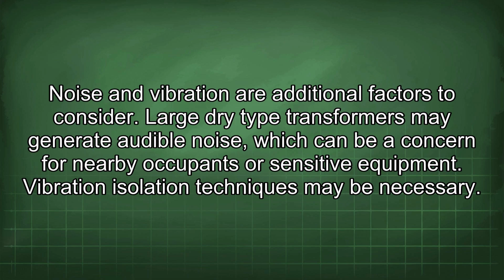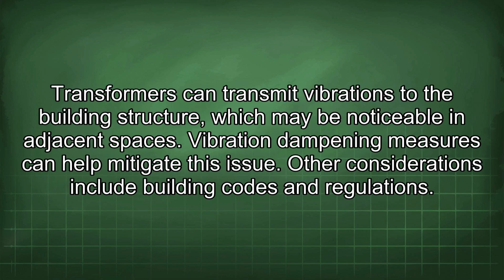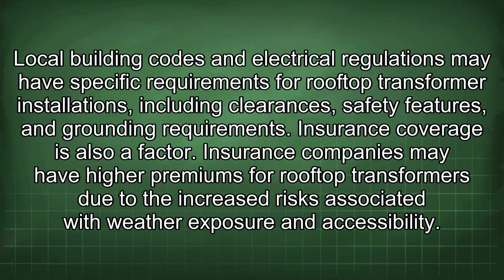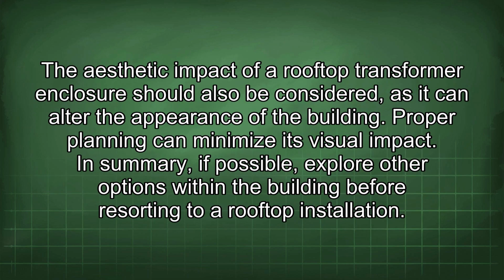Noise and vibration are additional factors to consider. Large dry-type transformers may generate audible noise, which can be a concern for nearby occupants or sensitive equipment. Vibration isolation techniques may be necessary. Transformers can transmit vibrations to the building structure, which may be noticeable in adjacent spaces. Vibration dampening measures can help mitigate this issue. Other considerations include building codes and regulations. Local building codes and electrical regulations may have specific requirements for rooftop transformer installations, including clearances, safety features, and grounding requirements. Insurance coverage is also a factor. Insurance companies may have higher premiums for rooftop transformers due to the increased risks associated with weather exposure and accessibility. The aesthetic impact of a rooftop transformer enclosure should also be considered, as it can alter the appearance of the building. Proper planning can minimize its visual impact.